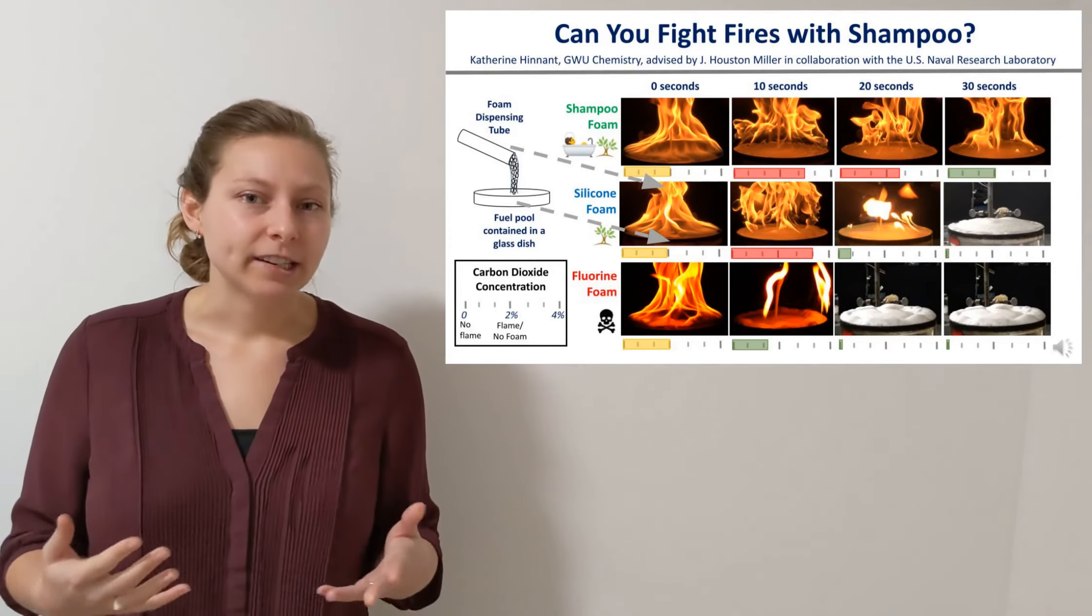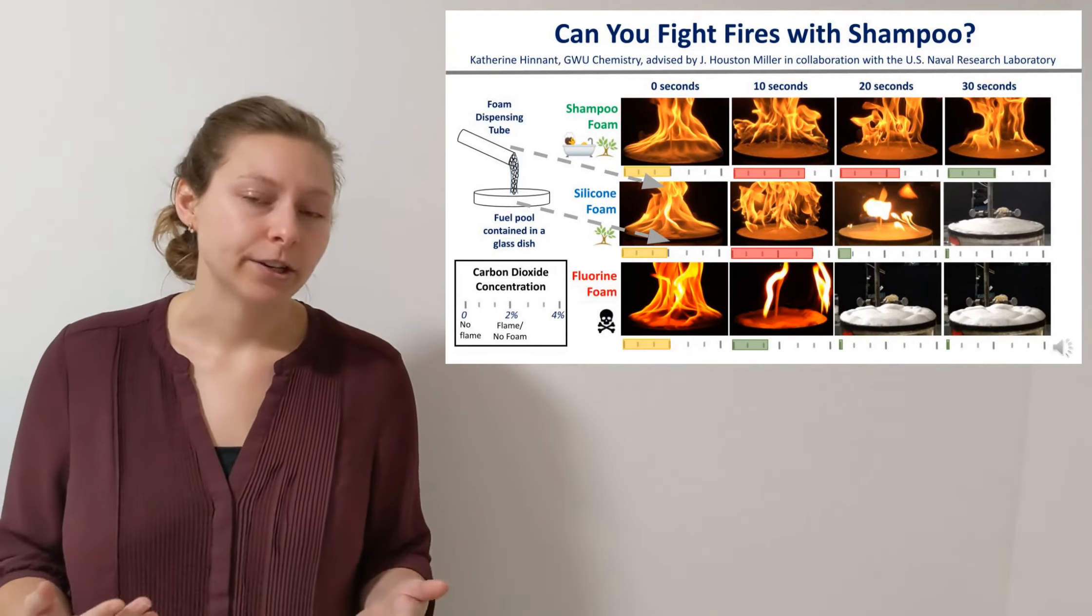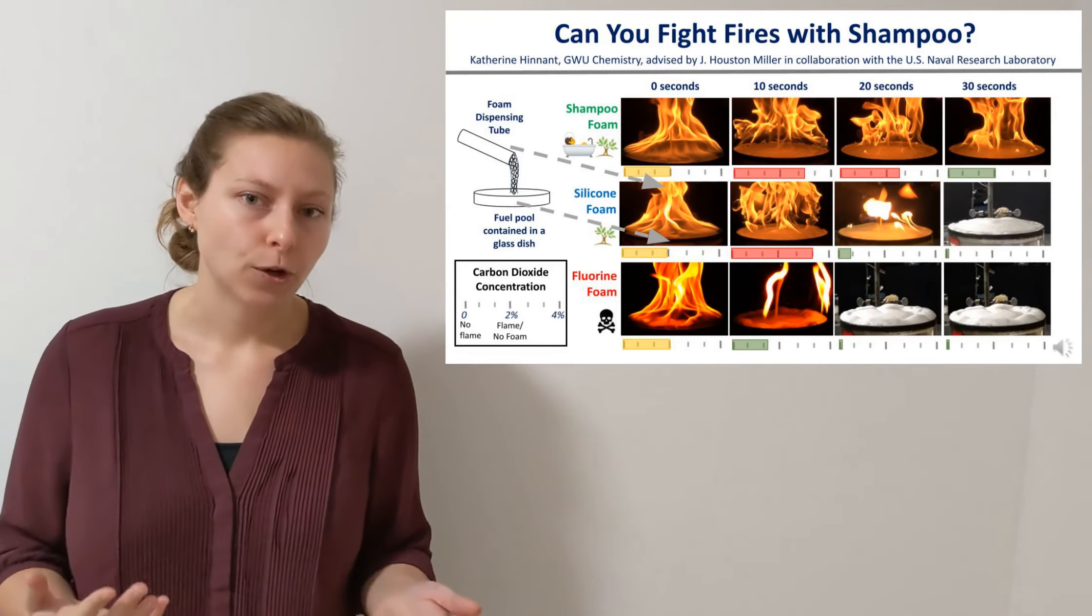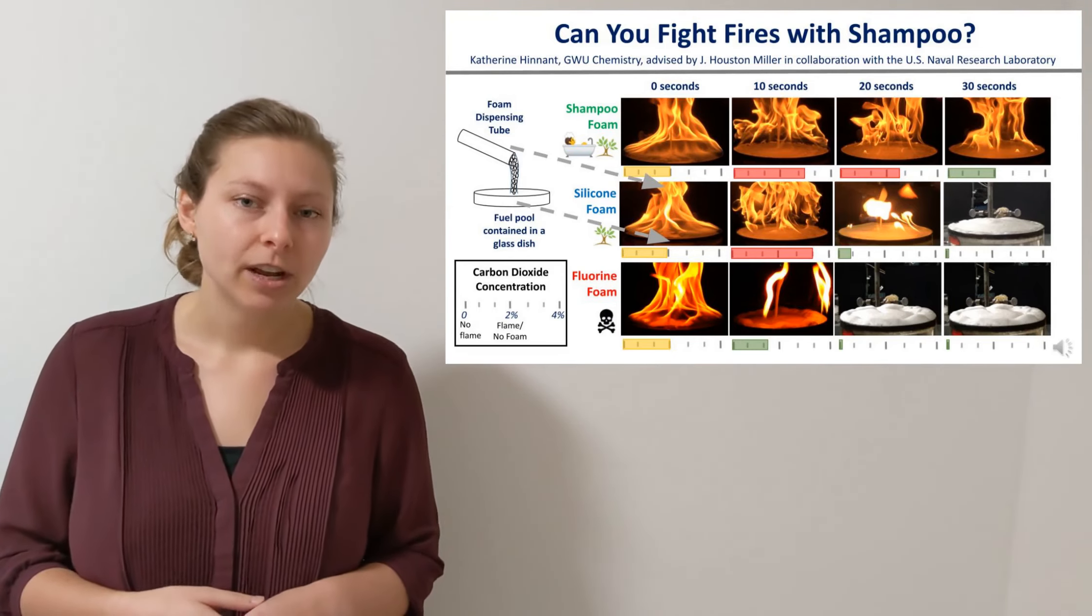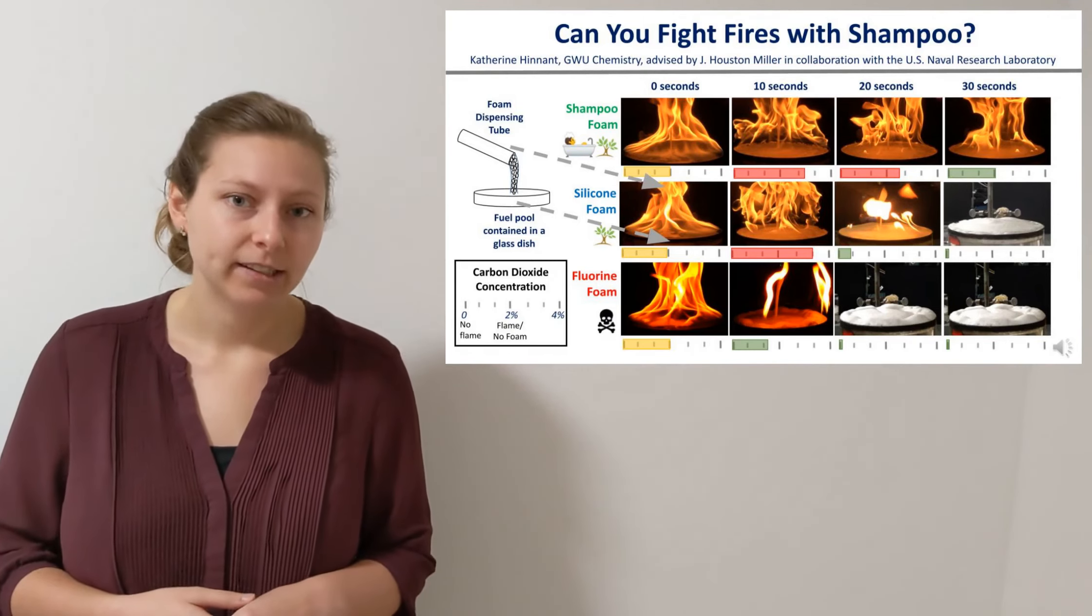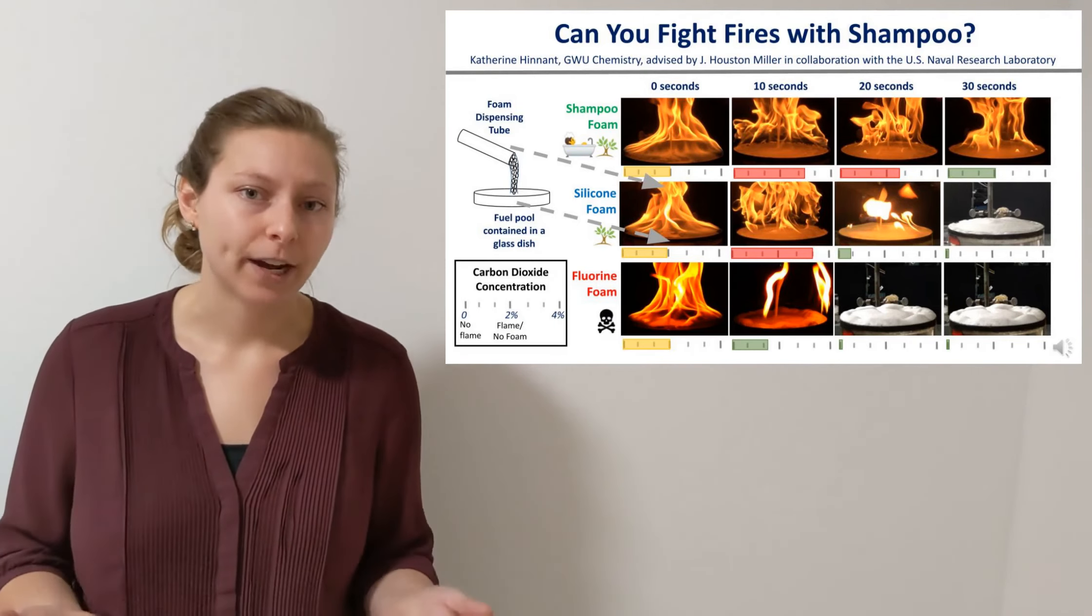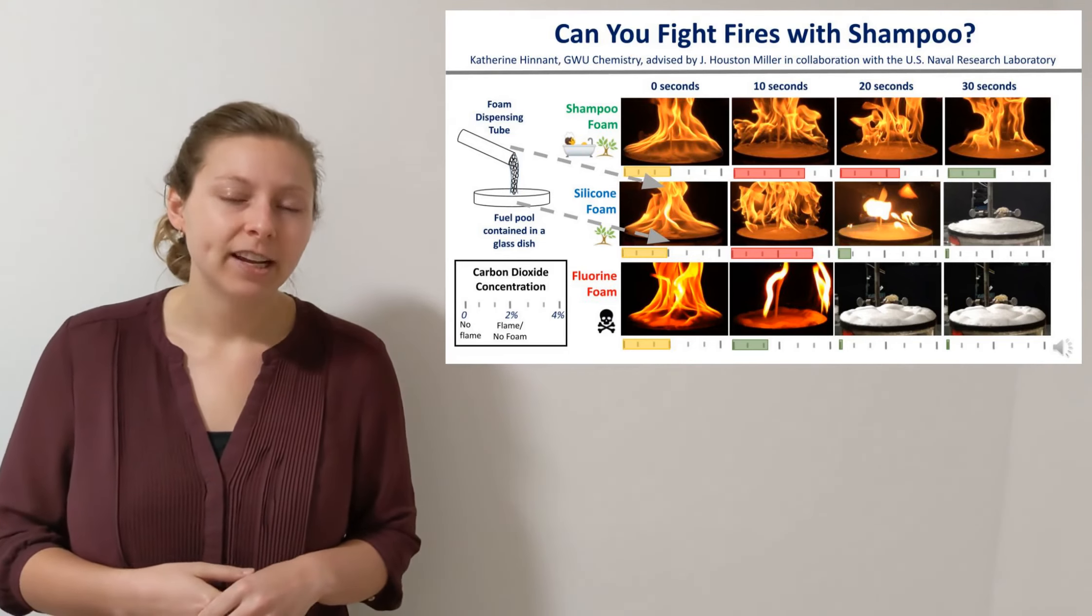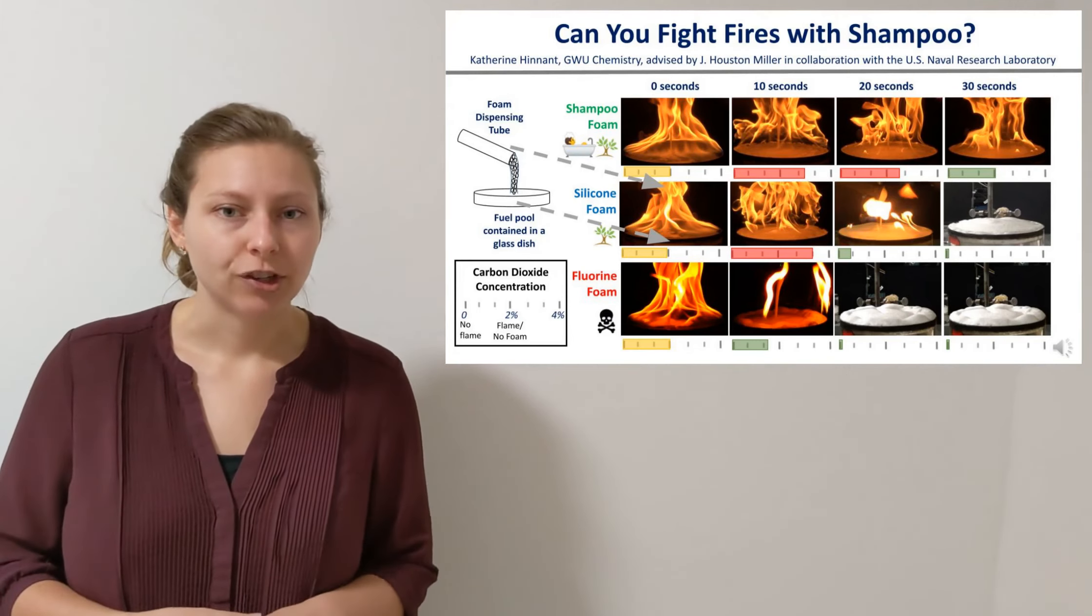Although we see differences in extinction time around 20 to 30 seconds, measured carbon dioxide data, also shown under each time-lapse image, shows differences in performance in as little as 10 seconds. Surfactants have an impact on fire suppression almost as soon as the foam hits the fuel surface, giving us insight into their role in fire suppression.